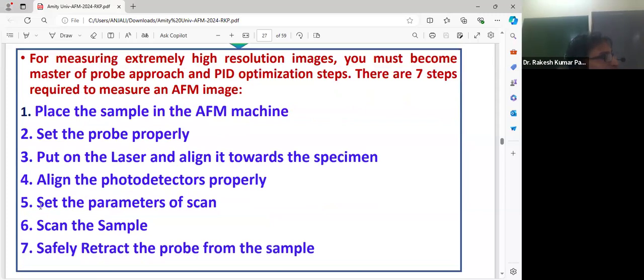The next point becomes very important in scanning: set the parameters properly. Nowadays AFMs come coupled with automatic software. Whatever parameters are there, you need to know the range of parameters and give an appropriate range. Otherwise it will become very difficult to scan properly. By putting in appropriate values of the parameters, you can easily scan.